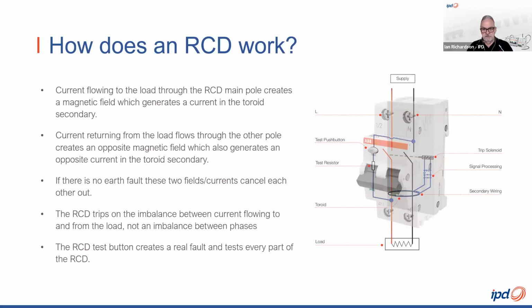So if there is no earth fault, these two magnetic fields and the currents will cancel each other out, and the net result obviously is zero. The same cancelling effect occurs if it is a single phase or a three-phase device. The RCD will trip on the imbalance between the current flowing to and from the load, not an imbalance between the phases. So this device is fine if there's an unbalanced load. Yeah, and the RCD test button creates a real fault by placing a resistance across the toroid and tests every part of the function of the RCD.